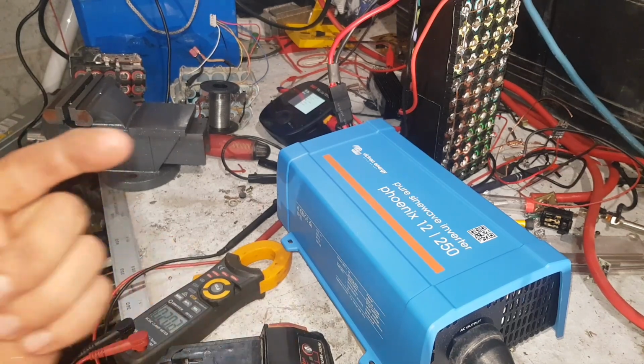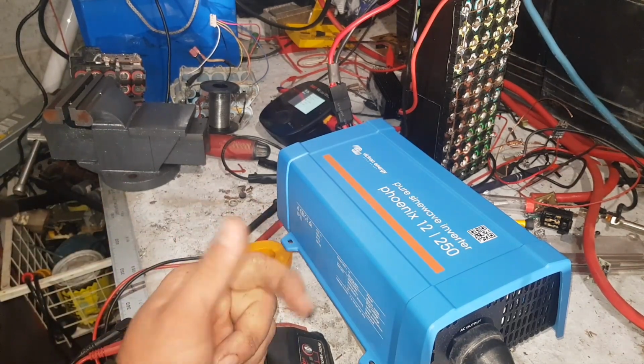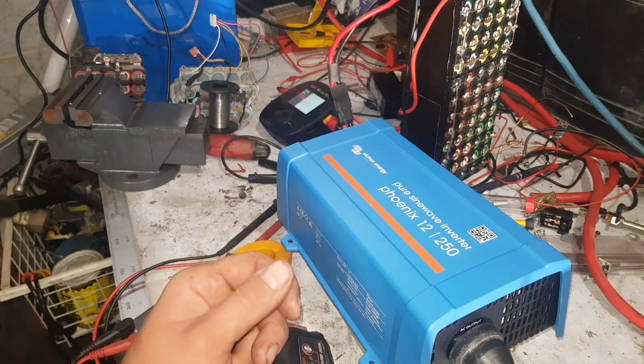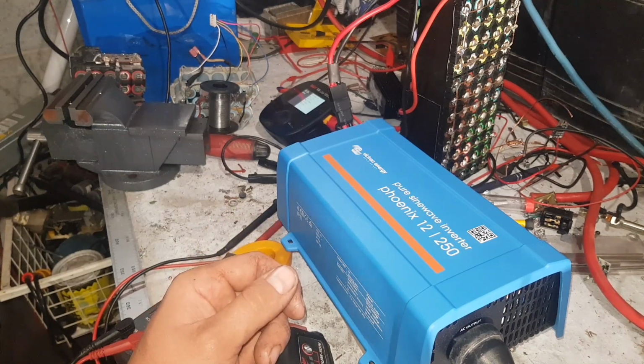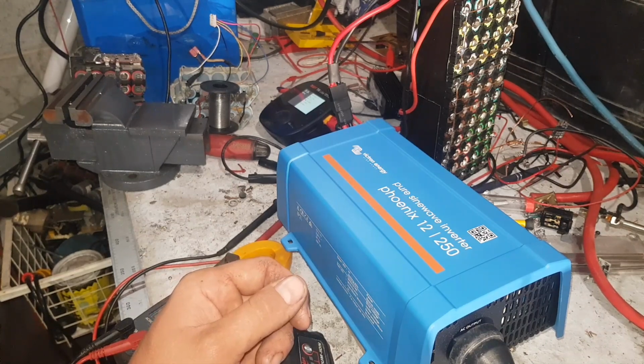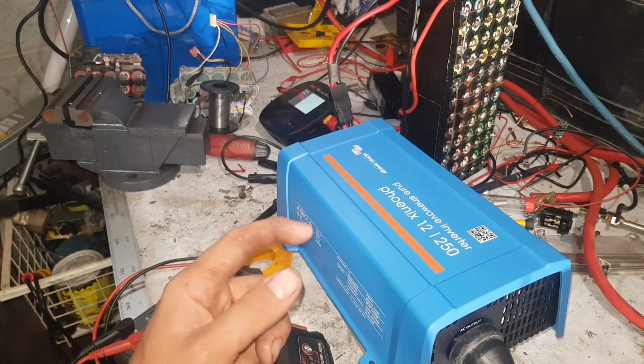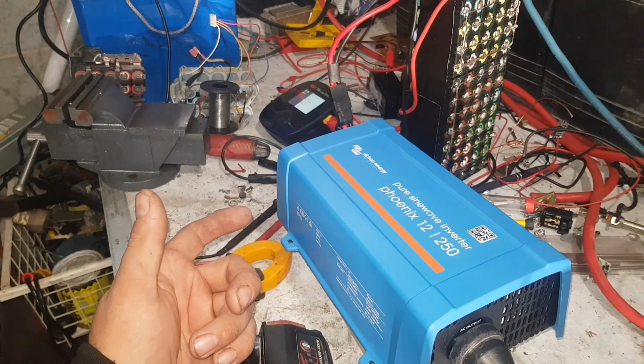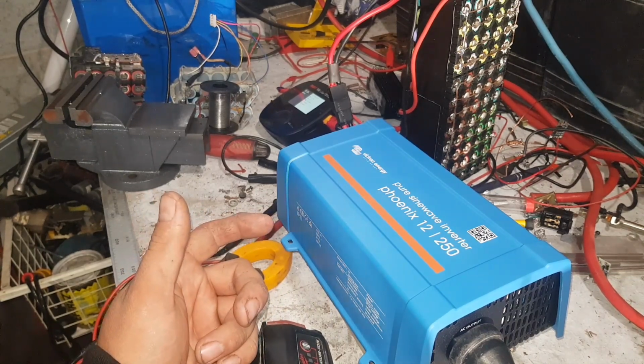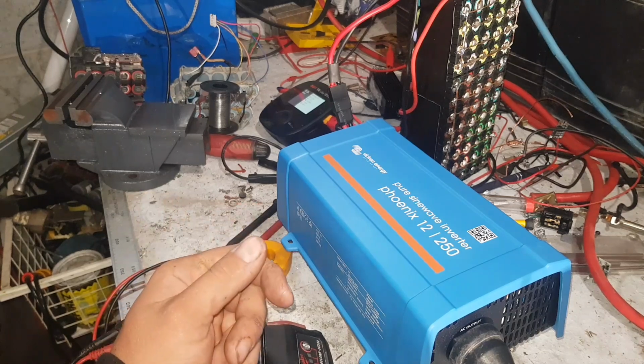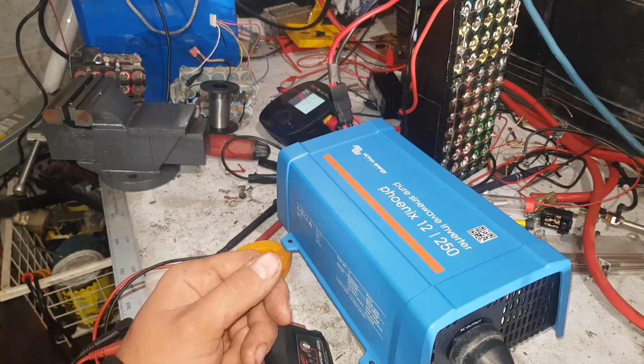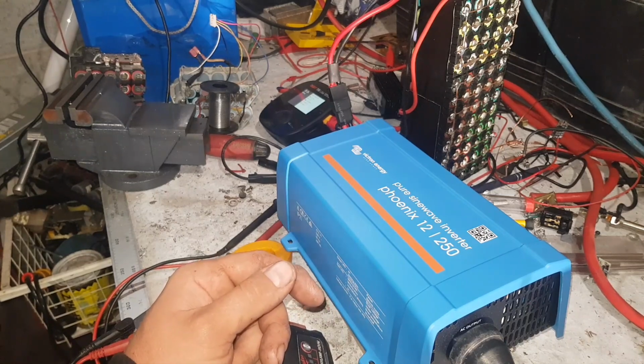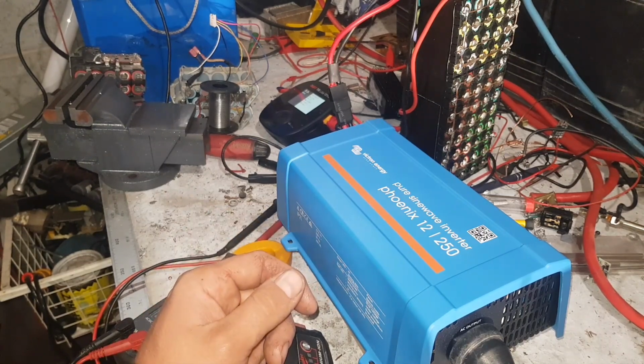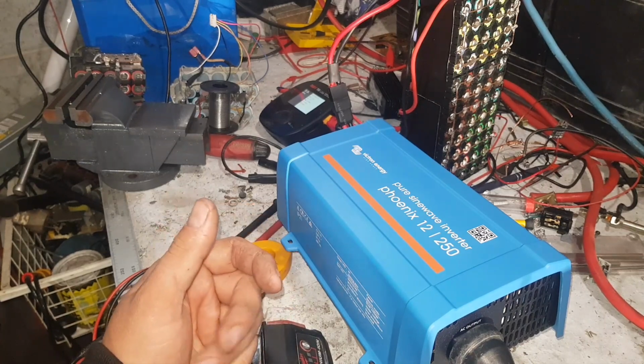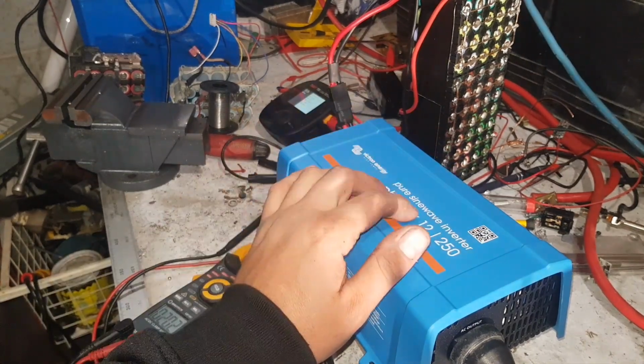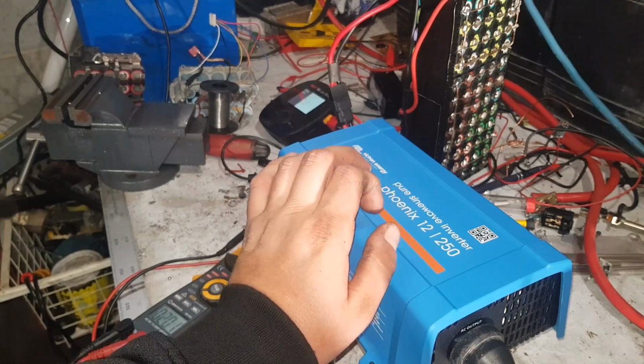Hope you enjoyed. This is my new Victron Energy Phoenix 12 250 pure sine wave inverter, which doesn't make any horrible harmonic noises and is probably what I should have bought in the first place. Cheap crap inverters are always going to be cheap crap inverters. If it's not somewhere near like a dollar a watt for the inverter, and if it's not Blue or Victron or a similar brand of high quality, you're risking your high-tech devices and your good devices. They're good for resistive loads, not inductive loads, not switch mode loads - keep that in mind.